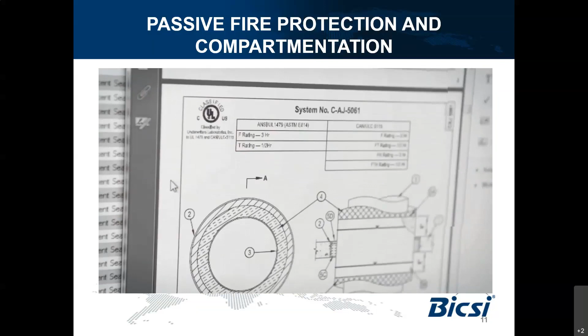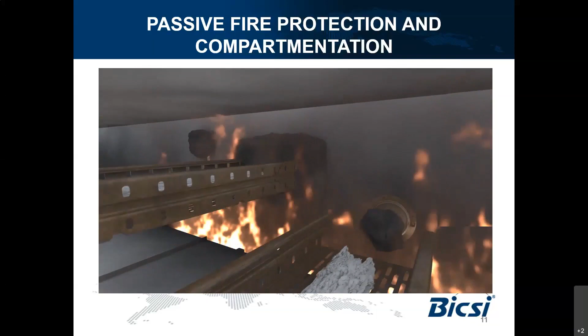The keys to effective fire protection are both active protection, such as detectors and sprinklers, but also passive protection. Passive means that penetrations in walls and floors have been sealed with approved firestop products. This principle is called compartmentation. When installed correctly, fire and smoke won't be able to spread from one compartment to another, allowing for safe evacuation of people and protecting valuable assets.